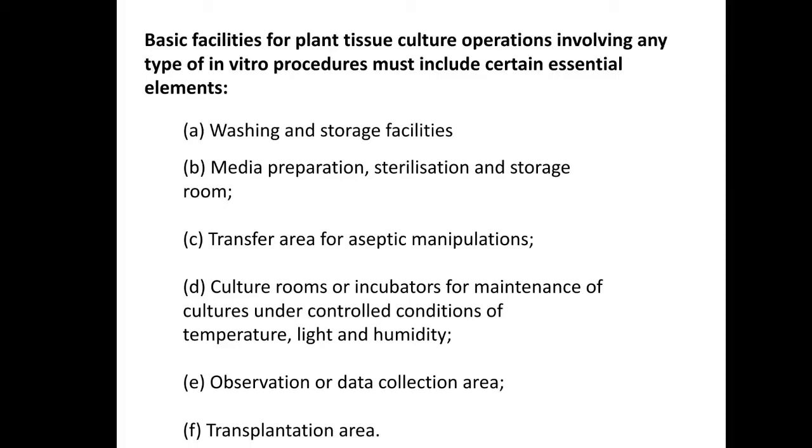And here the shelves should be designed in such a way so that the culture vessels can be placed in the shelves or the trays in such a way that there should not be any difference in the light, temperature, and the humidity maintenance. And a label should be stuck on each tray and the rack to ensure the identity for maintaining the data of the experiments.